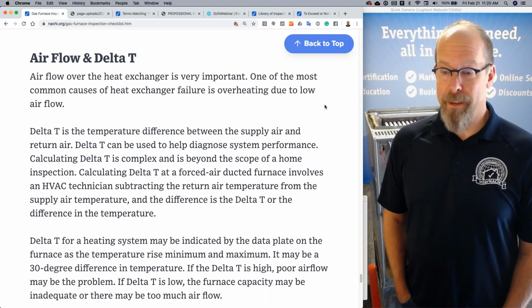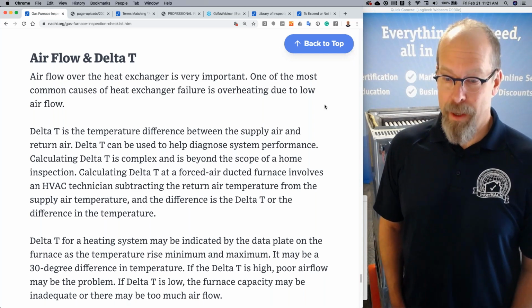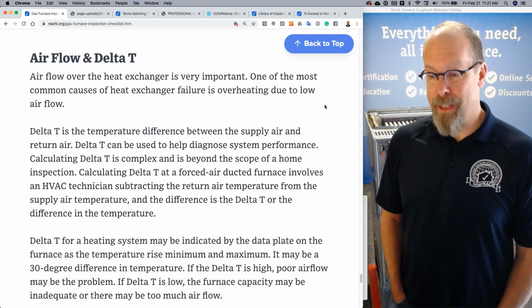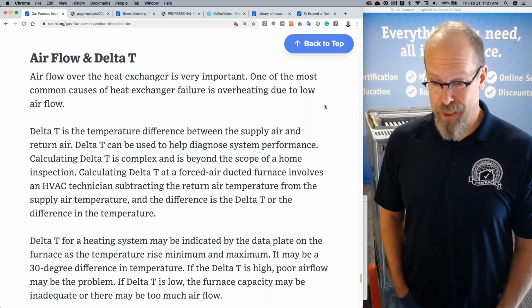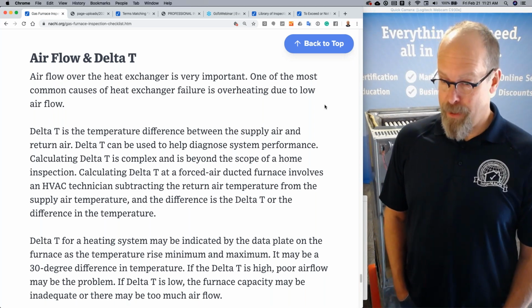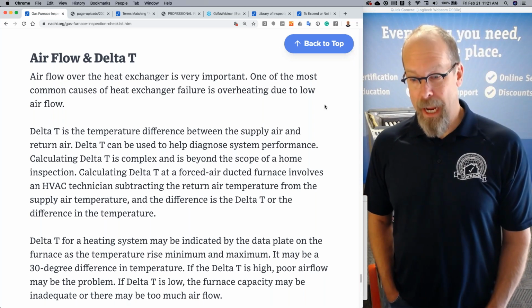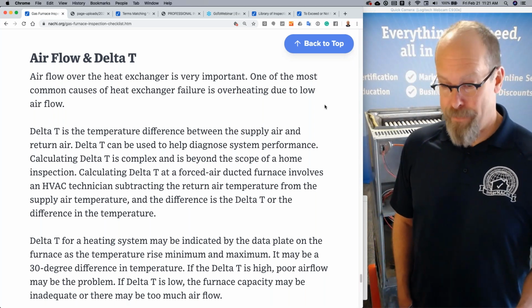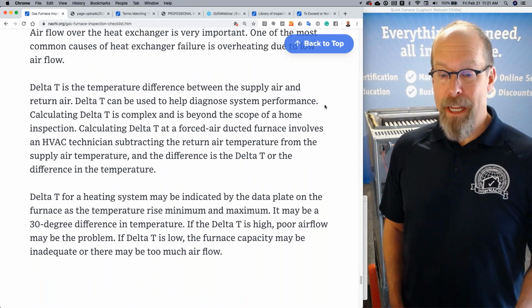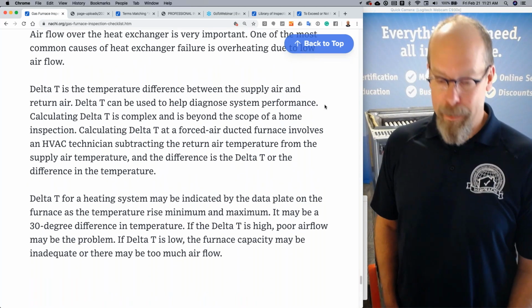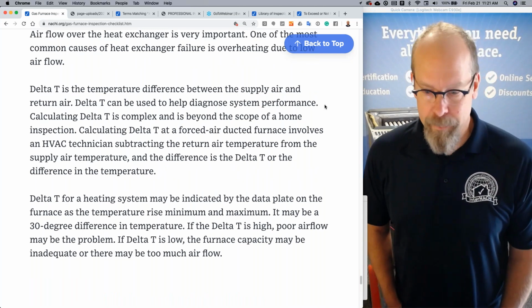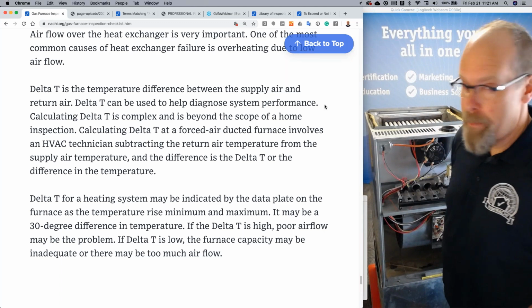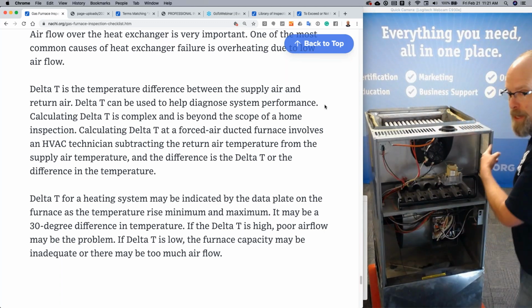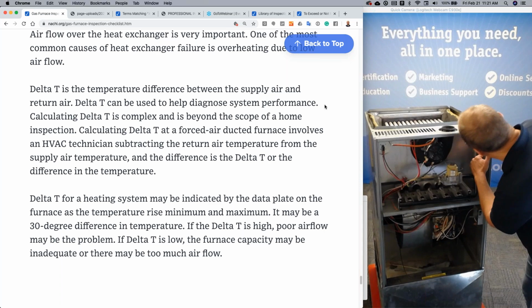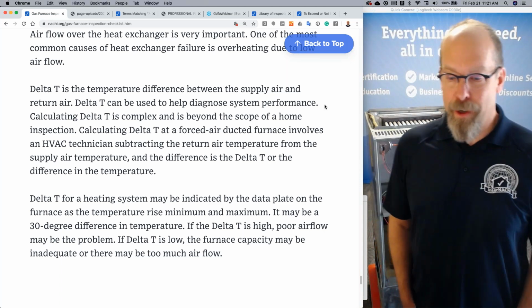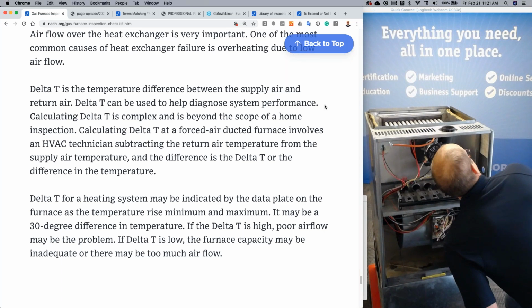Calculating delta T is complex and is beyond the scope of a home inspection. Calculating delta T at a forced air duct furnace involves an HVAC technician subtracting the return air temperature from the supply air temperature, and the difference is the delta T. Delta T for a heating system may be indicated by the data plate on the furnace as the temperature rise minimum and maximum. Actually on this system, it's right over here on this plate, and there it is. It may be a 30-degree difference in temperature, and actually it is.